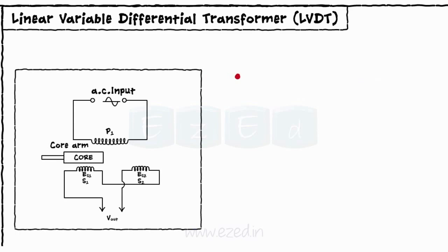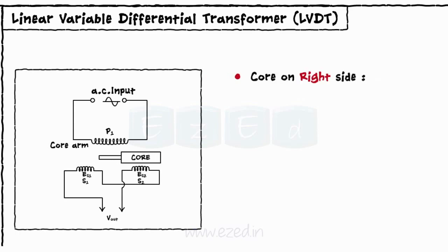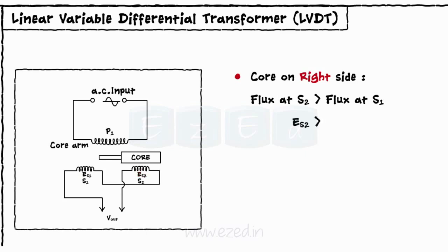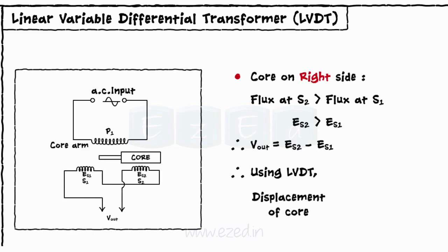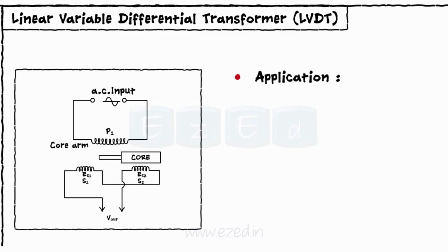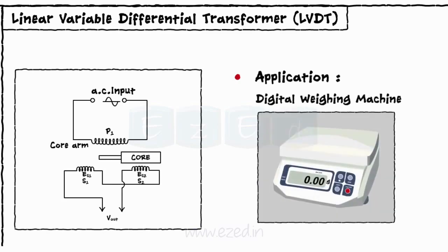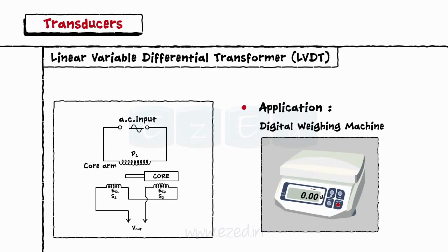Thus, using LVDT, the displacement of a core is converted into an equivalent electrical signal. Similarly, when the core shifts towards secondary winding S2 due to displacement, more magnetic flux gets linked to coil S2 than S1. Hence, the EMF induced in coil S2, ES2, is more than ES1. Thus, the output becomes Vout equals ES2 minus ES1. Using LVDT, the displacement of a core is converted into an equivalent electrical signal. LVDT is commonly used in digital weighing machines, along with a load cell, which we will see shortly.